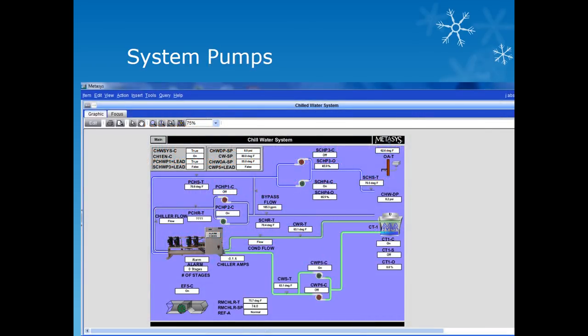In the system shown by this graphic we have one chiller served by two primary chilled water pumps, two secondary chilled water pumps, and two condenser water pumps. The purpose for having so many pumps is due to the redundancy required in a critical area. If one pump were to fail we could lose the entire chilled water system. With this configuration we have the option of simply switching to another pump to keep the system online.